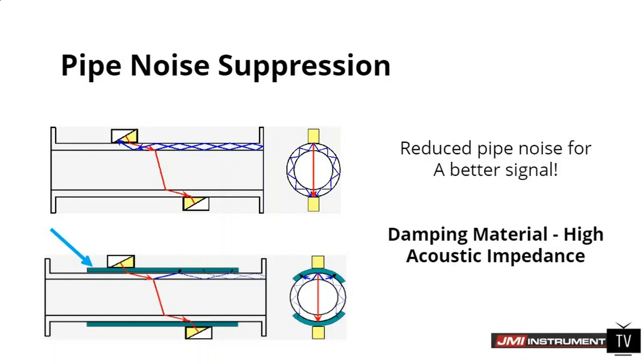And that's simply because the pipe is way more dense than the gas. So the sound signal likes to take the path of least resistance. So it likes to ride in this very dense metal. So if we only get, say, 10% of our signal across, and we have 40% of our signal as noise, we'll have a negative signal to noise ratio. But we put this dampening on, and it decreases the noise on the pipe to be able to get us a positive signal to noise ratio.